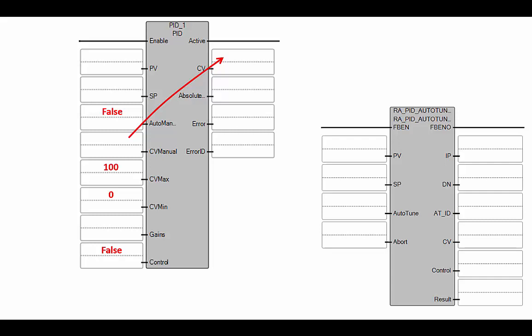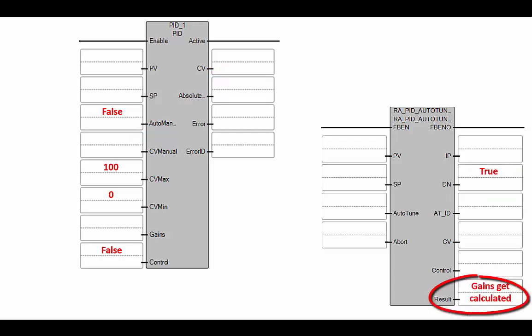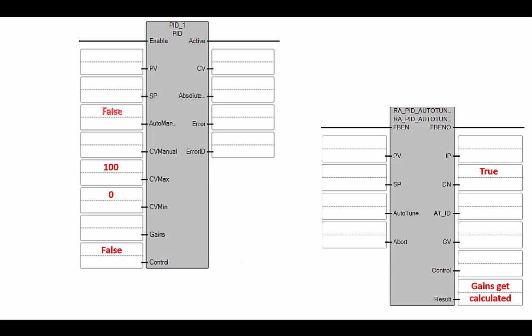Basically, if we put the PID in manual mode and the auto-tuning instruction in auto-tune mode, then the CV from the auto-tuning instruction is what's actually controlling our process. You'll see that auto-tuning will increase and decrease the level of the tank to get a feel for the oscillations. Once the auto-tuning has finished its procedure, the done bit will become true and the result output will have our calculated gains. If we then pass these gains into the PID controller and turn it to automatic mode, our PID controller will control the process using the new gains.